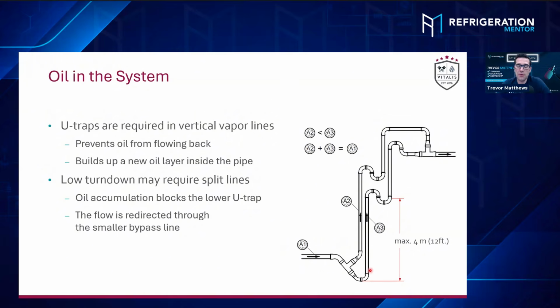Yeah, and that's so important, to have an inverted trap at the top. And then, as you see where he has the bushing there, the bushing's on the horizontal, not on the vertical. Because honestly, when I first started installing these, I wasn't sure if I needed to put the bushing on the bottom and just have the riser or put it there. So I've done it both ways. Then I learned that you need to put the bushing on the horizontal because that line can have oil in it. Just that little 1 mil, whatever it is, there could be oil that needs to go back and not go down into your trap. So good. Yeah. Love that.